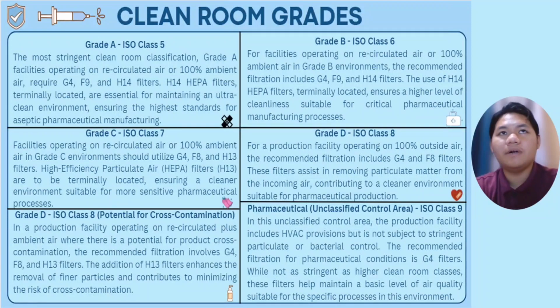Okay, I will tell about the clean room grades. I will simplify all of this so it will be easy to explain. For grade A, ISO class 5, it is a highly controlled environment for aseptic manufacturing. The filtration used for this is G4, F9, and H14 filters. HEPA filters are terminally located for this one. For grade B, ISO class 6, a facility with recirculated or 100% ambient air. Filtration for this is G4, F9, and H14 filters. HEPA filters are terminally located.